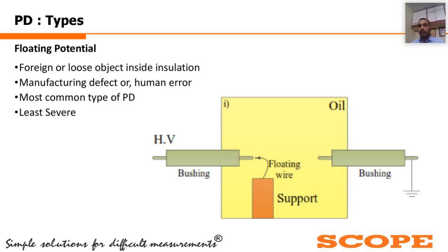So what happens is, as you have created some distance, you have disturbed the electromagnetic equilibrium of this particular insulation. So this loose connection leads to ionization in this medium. And as we are dealing with AC, that is alternating current, with change of the polarity of our signal, the charges keep on jumping from one source to the other. By one source or the other, I mean when the contacts are loose, both are basically the sources, right?